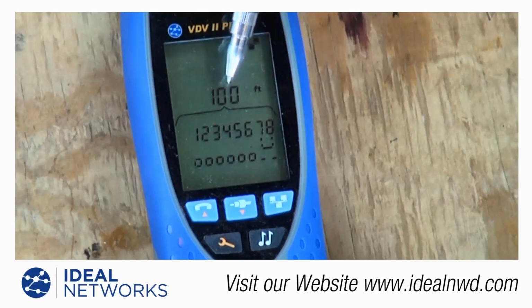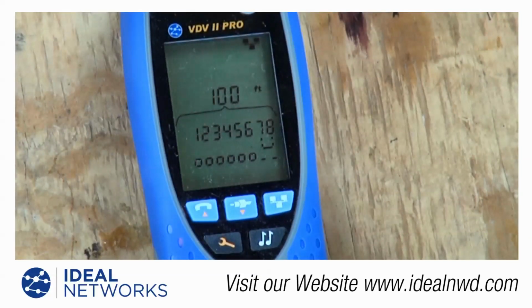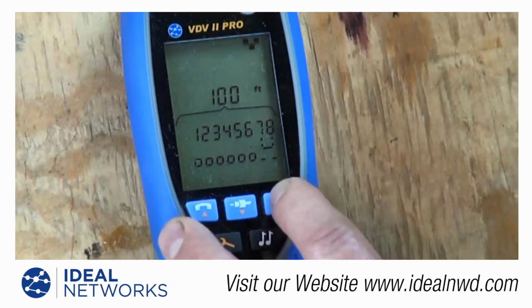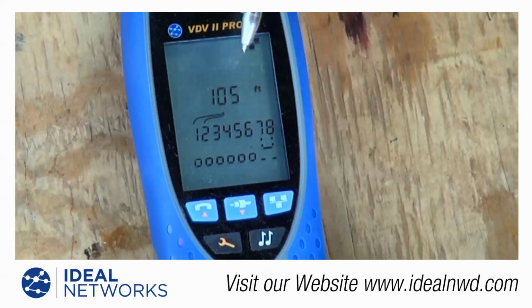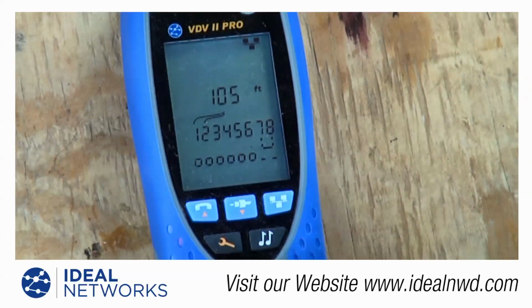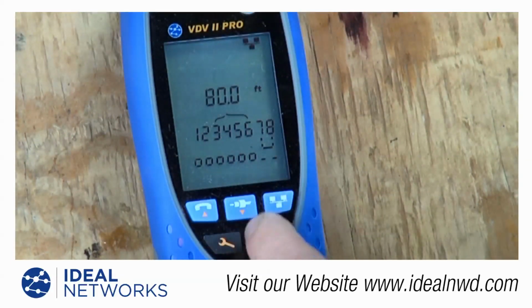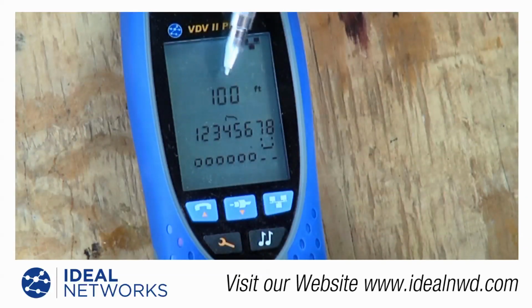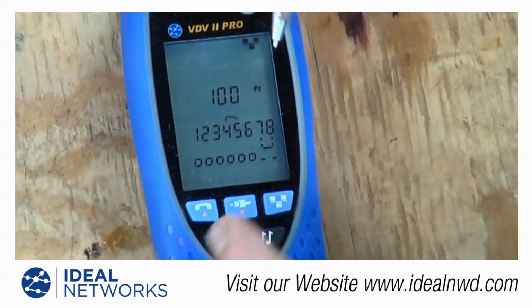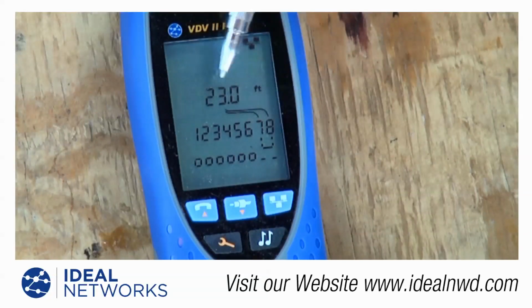This number is actually the length of the middle pairs, and since all pairs are twisted differently, they're each a different length. Pins 1 and 2 are about 105 feet long, 3 and 6 are about 80 feet, 4 and 5 are about 100 feet as expected, and 7 and 8 are about 23 feet.